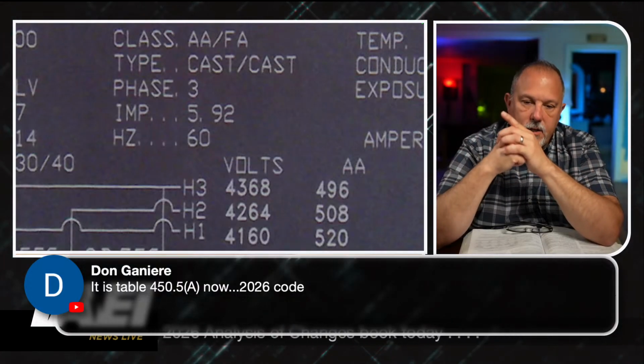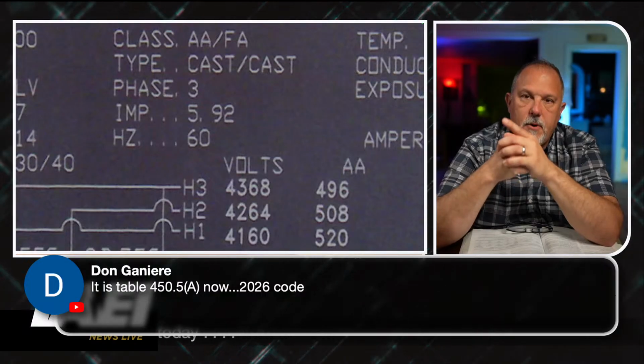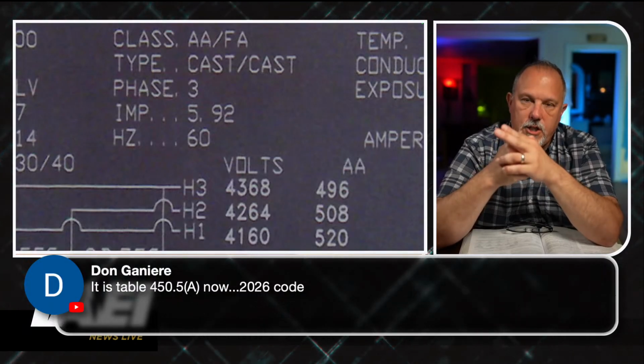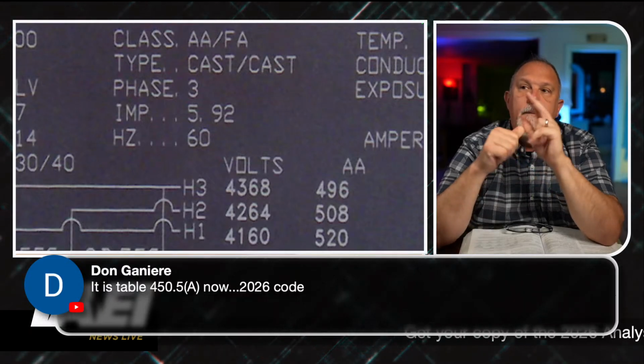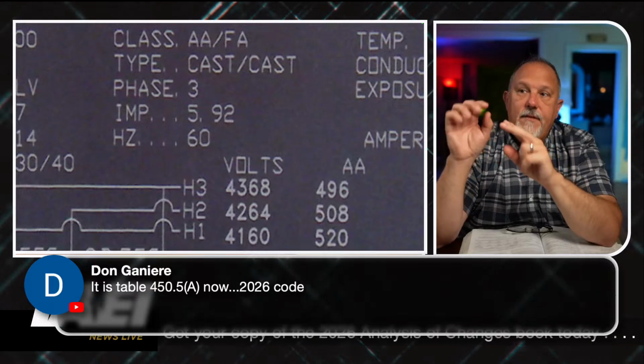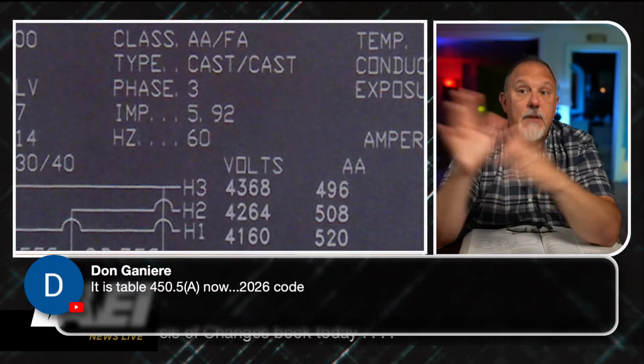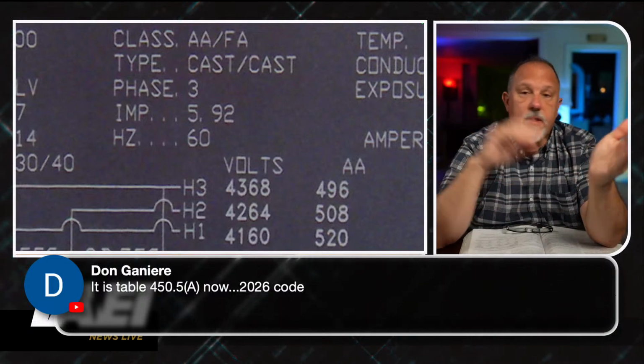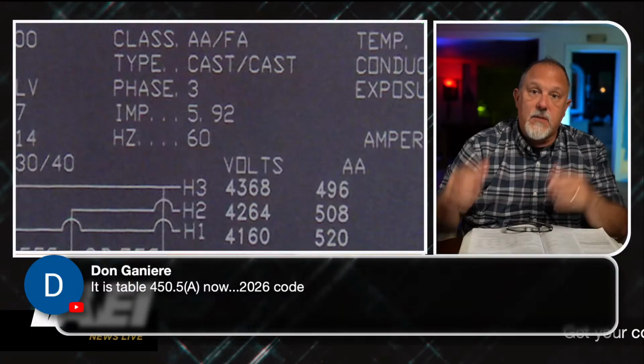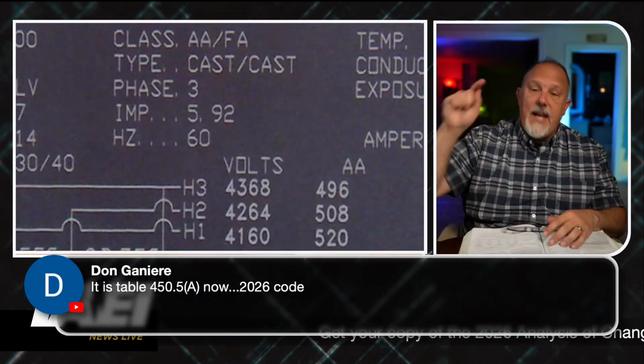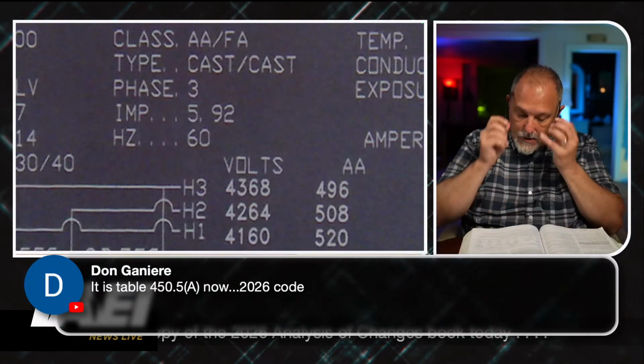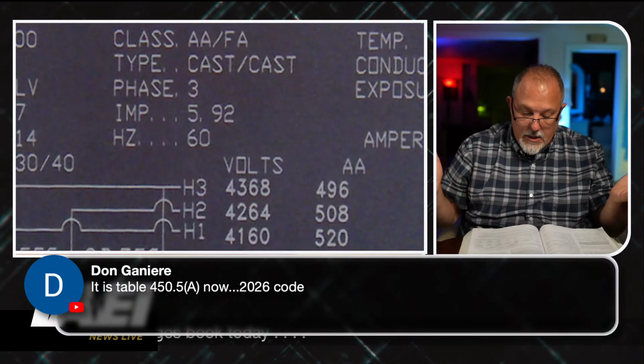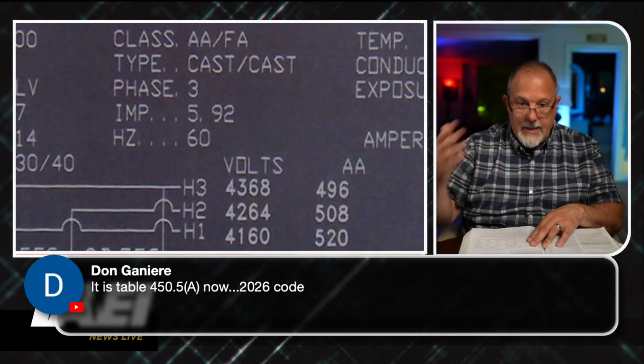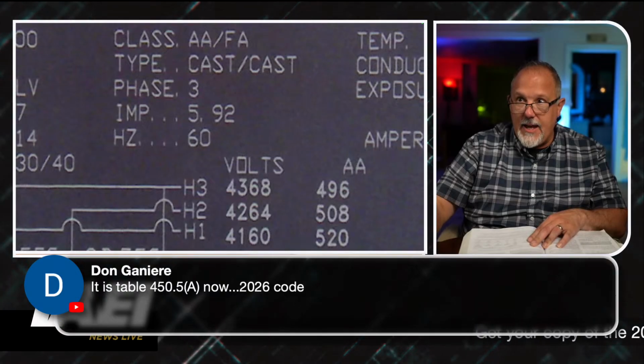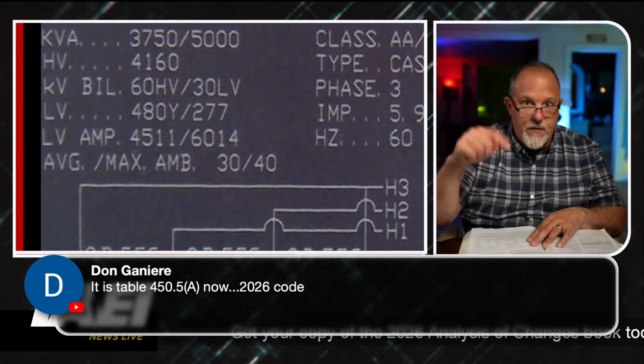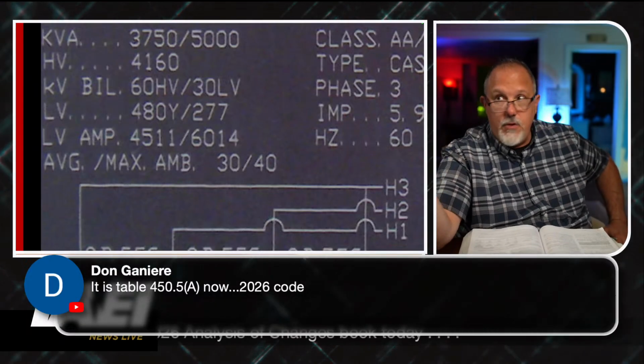So my impedance is not going to change based upon whether or not I have fans. My inrush current's not going to change based upon whether or not I have fans. So I have the ability to pick an overcurrent protective device that would work for both with and without fans. I've got to think about with and without fans, is my point. Now, if this was FFA, future fans added, there's nothing in the code that tells me I need to size my overcurrent protection and consider the higher kVA, this 5,000 kVA.